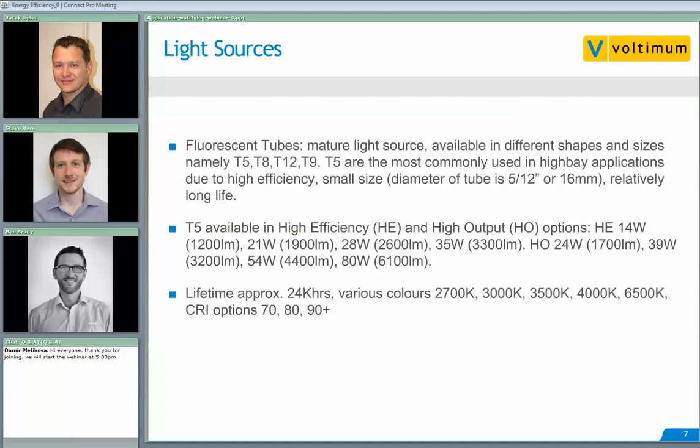The next light source is fluorescent tubes — also a mature light source available in different shapes and sizes, mainly T5, T8, T12, and T9 circular types. T5 are the most commonly used in high bay applications due to their high efficiency, relatively small size — diameter of about 16mm — and relatively long life. T5 are available in high efficiency (HE) and high output (HO) versions, ranging from 14 watts through to 35 watts for HE, and 24 watts to 80 watts for HO, where 80 watts gives about 6,100 lumens. Typical lifetime is about 24,000 hours.